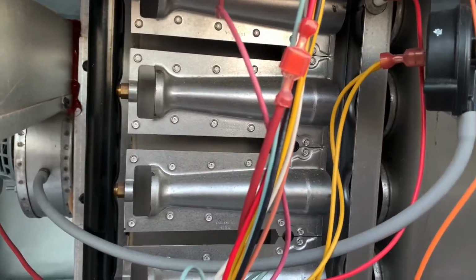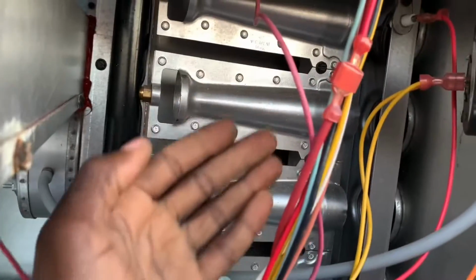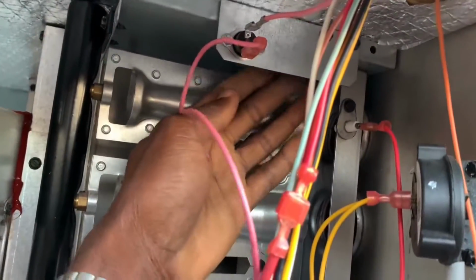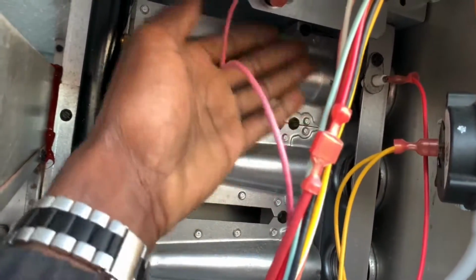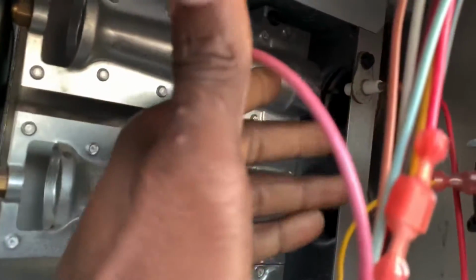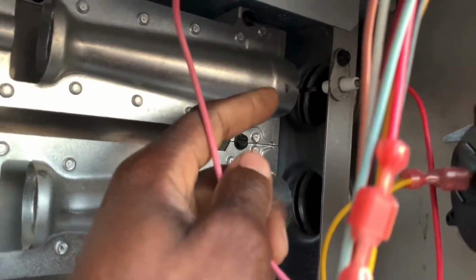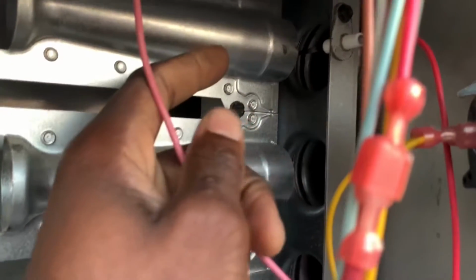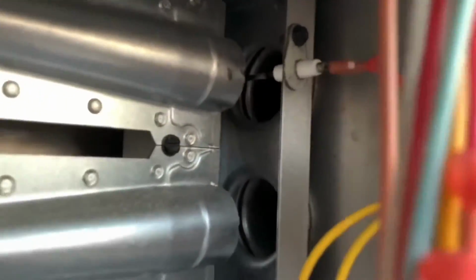Now, if the flames are rolling out, meaning it's burning in the back, over here in this area, there's fire back here, burning in this general area. The flame should be, I'm going to restart the furnace and you will see how the flame goes in, right? It goes into those holes. It goes straight in. There's no fire back here, or burn out here.